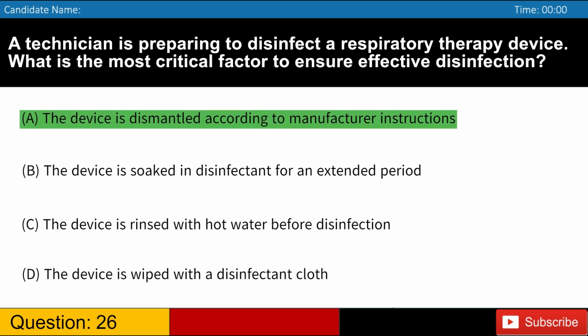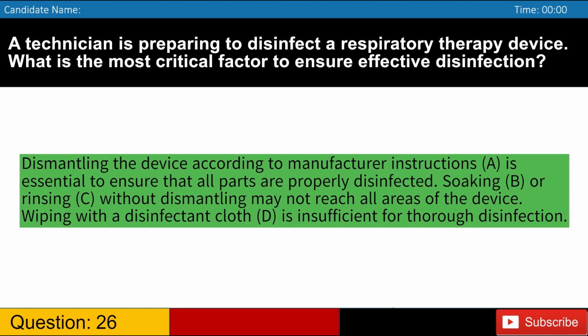Answer, A. Dismantling the device according to manufacturer instructions, A, is essential to ensure that all parts are properly disinfected. Soaking, B, or rinsing, C, without dismantling may not reach all areas of the device. Wiping with a disinfectant cloth, D, is insufficient for thorough disinfection.